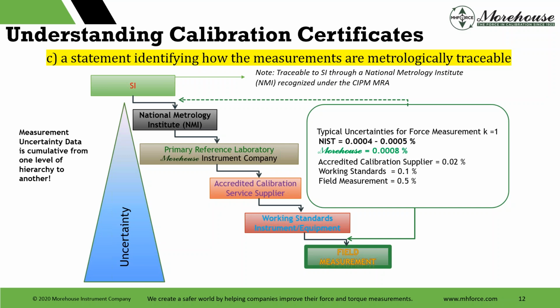And when we start doing this, obviously NIST can achieve a better level than us on uncertainty, and that data is cumulative as far as every level down gets bigger and bigger. So when we look at traceability here, we see NIST, this is for K equals 1, that's one standard deviation. NIST is 4 to 5 parts per million. Morehouse is right here, this is what we are, 0.0008. Accredited calibration suppliers are 0.02, then working standards and field measurements. These are typical for force, and as you can see, they get larger and larger.